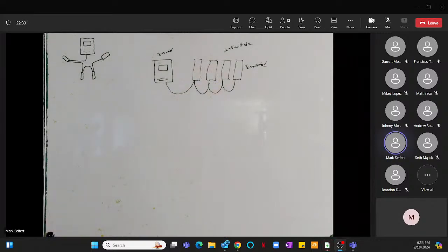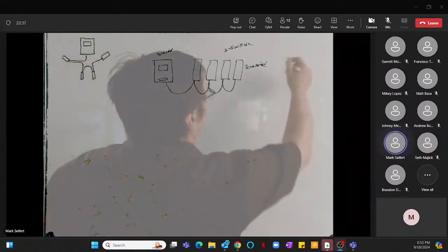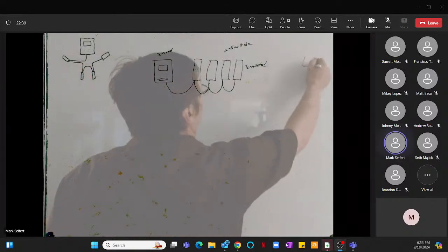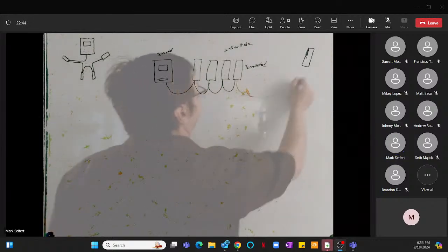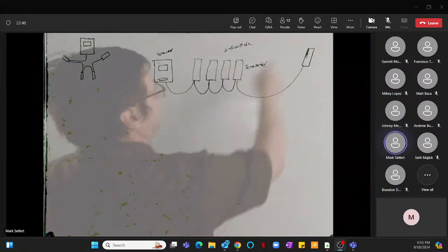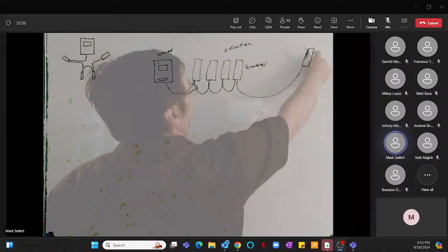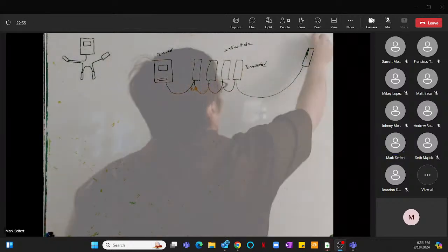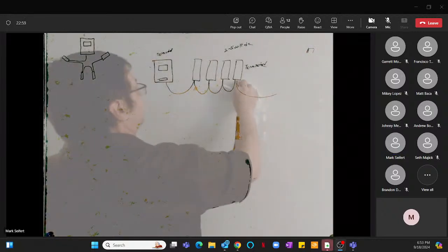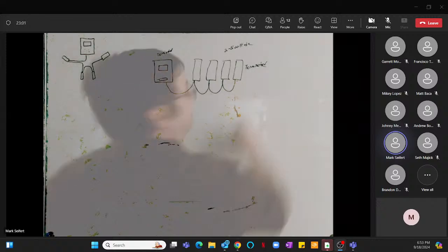So if you're having comm problems and you find that maybe a long time ago this one used to have a board out here on a condenser and that's gone now, and they've removed that board, well, it used to be this one would have been terminated, and if they removed it and didn't terminate this one, you could run into problems. So that's always something to check. Make sure it's terminated.